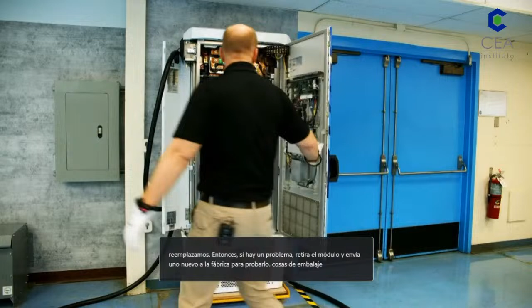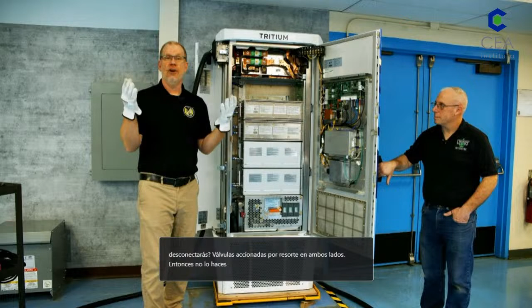So these are all liquid cooled, so there's liquid in here right now. This thing is fully charged, ready to go—if we plugged it in, it would operate. We've got liquid cooling lines, so the first thing I'm going to do is disconnect them. These automatically shut off; when you disconnect it, spring-loaded valves on both sides mean you don't have to worry about leakage or air getting into the system. You never have to bleed the system. So it's just a quick disconnect, and I can pull the hoses up out of the way.